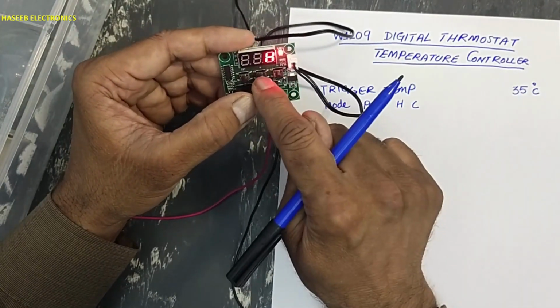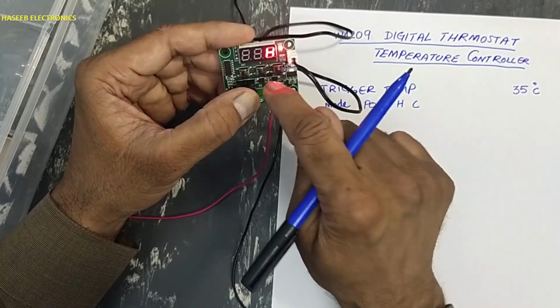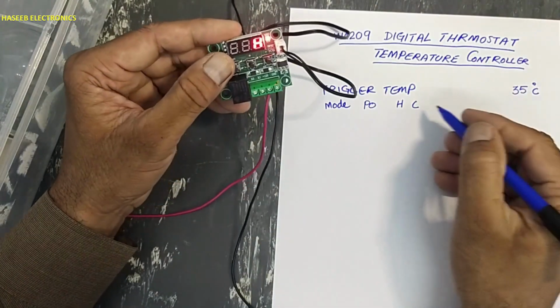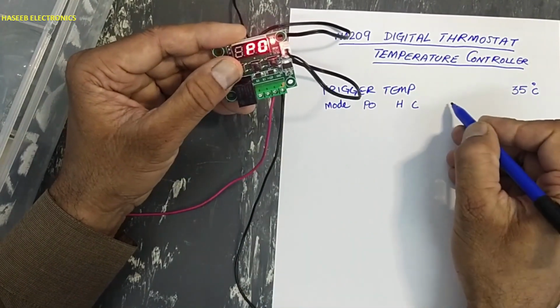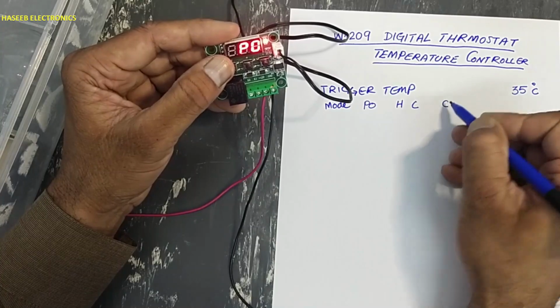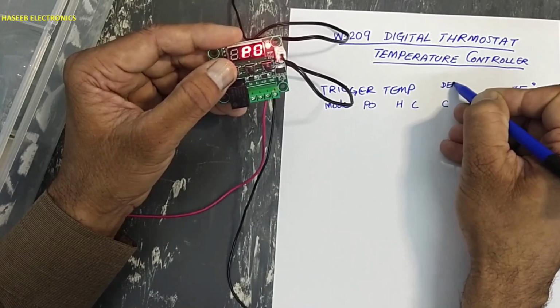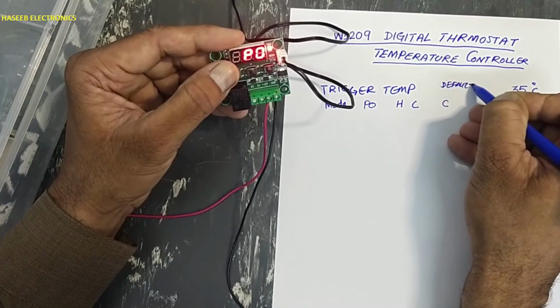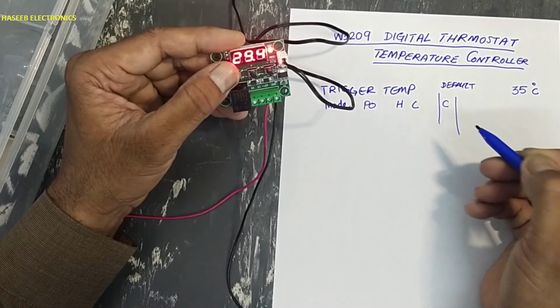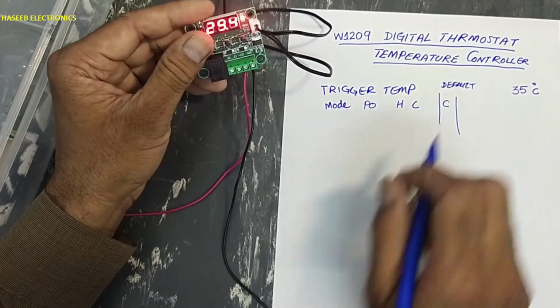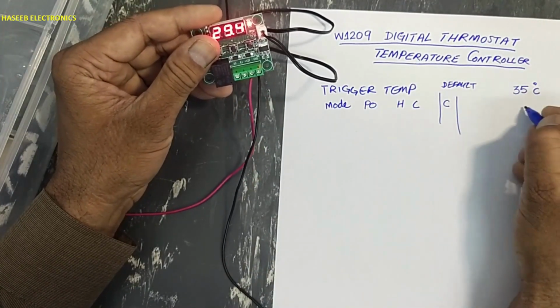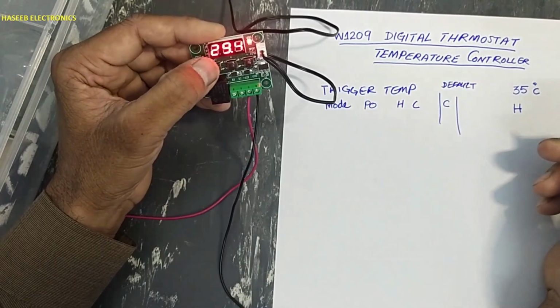We can press plus button or minus button to toggle the values. Here H, press set button. The default setting is C. Here is the default setting. Now we adjusted it for our requirement, heat mode.